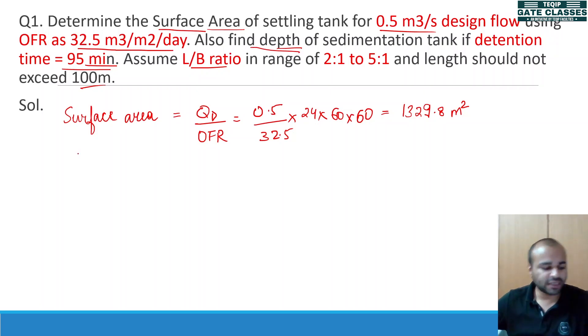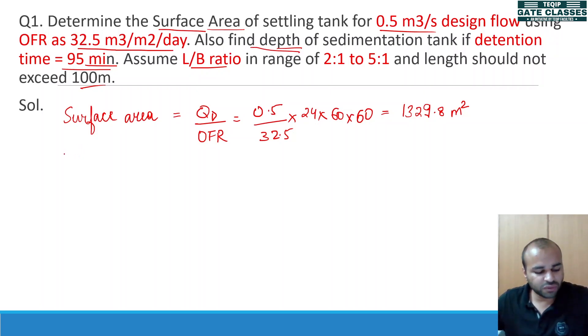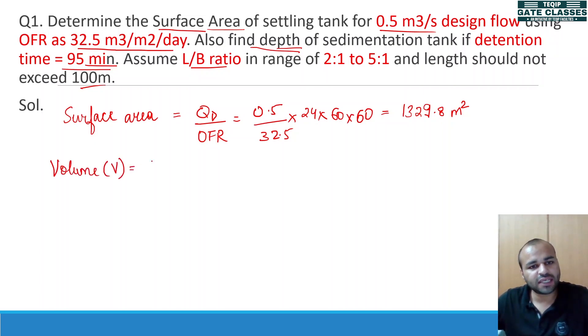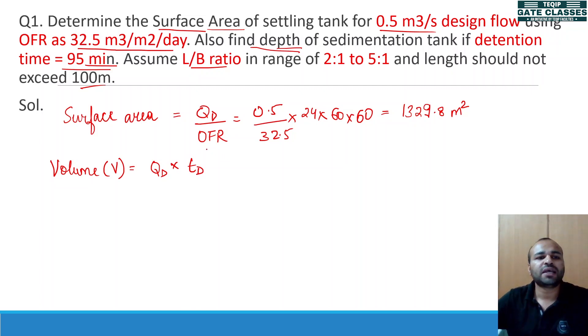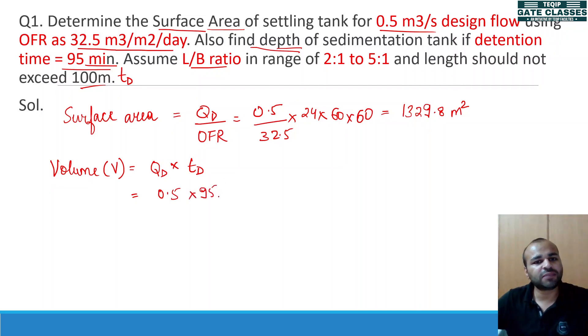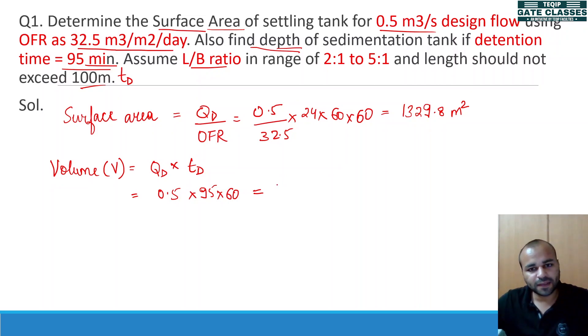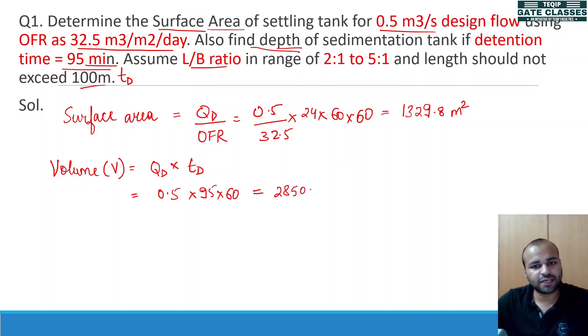Now we also need to find the depth. To find the depth, we need to calculate the volume. Volume V can be calculated using the discharge multiplied by the detention time. Here the detention time is 95 minutes, so: 0.5 × 95 × 60 seconds. The final value comes out to be 2850 m³.